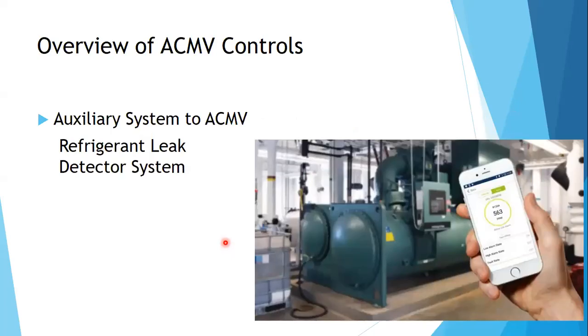Another one is the refrigerant leak detector system. Since your chillers have compressors, they are also using refrigerants. Sometimes there are refrigerant leaks. Refrigerant leaks are colorless and odorless deadly gas. So you would need a refrigerant leak detector system around your chillers.